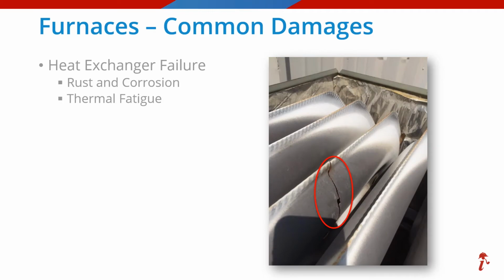There's also a process known as thermal fatigue, which is the gradual deterioration and eventual cracking of the metal by alternating heating and cooling. The fact is, if you use a furnace often enough and for a long enough period of time, thermal fatigue is an eventual certainty. It is accelerated by the corrosive combustion gases that pass through the heat exchanger tubes on their way to the exhaust flue and by condensation that may collect in the heat exchanger during heat transfer. Some manufacturers are crimping joints instead of welding and applying special alloys to slow the thermal fatigue process.